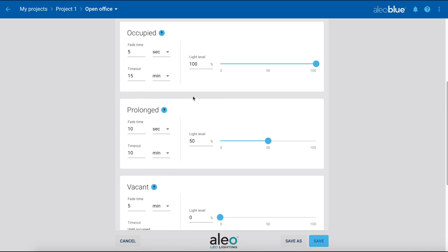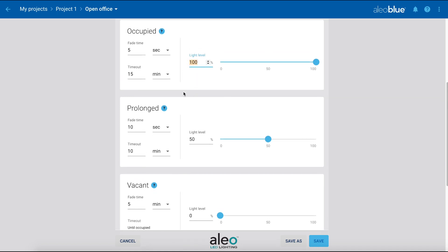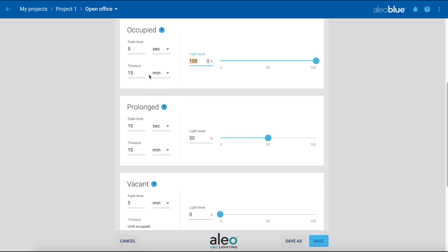With these settings, when occupied, the zone will be at 100% light level. After 15 minutes of no occupancy, the lights will dim down to 50% with a 10 second fade down. After 10 minutes of no motion during the prolonged stage, the lights will dim down to off until motion is detected again.